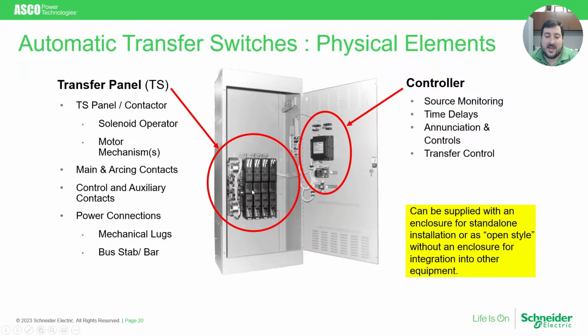It is the device that is actually carrying the current from the sources to the loads, and that's doing the physical switching of the equipment. And in many cases, also the enclosure in which these two pieces of equipment are mounted in. The controller and the switch are mounted inside an enclosure in many applications, indoor enclosures, outdoor enclosures, or in some cases, no enclosure is provided so that the switch and the controller can be mounted into other pieces of equipment or switch gear, to integrate a solution.